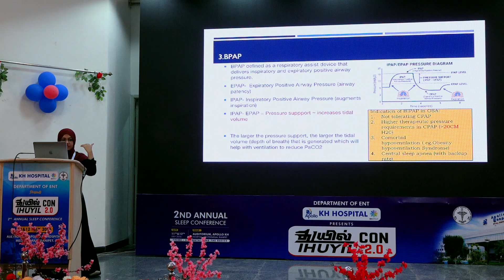So this is adaptive servo ventilation. It is not quite commonly used. It is a device which has a servo controller, which is a computer-controlled valve. It will adjust the airway pressure on a breath-by-breath basis to maintain the ventilation. So the way to remember is that CPAP has one fixed pressure, BiPAP has two fixed pressures. Adaptive servo ventilation is a device where EPAP is kept constant, but IPAP keeps varying depending upon the patient's breathing pattern. So it is especially beneficial for patients who have periodic breathing, like Cheyne-Stokes breathing in heart failure.